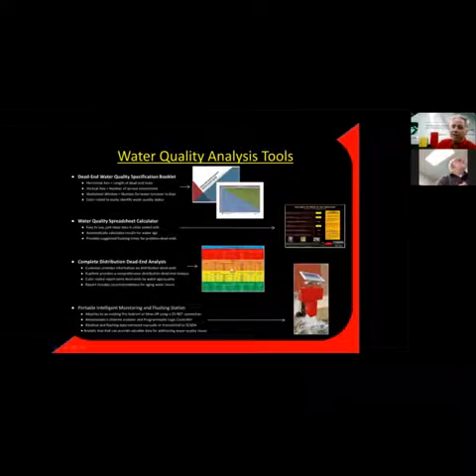Another very effective tool we have is what we call intelligent monitoring and flushing stations. This portable monitoring and flushing technology is an analytical tool that attaches to a fire hydrant. I can program it to maintain a certain residual or turbidity. It has a PLC and a chlorine sensor, and I can tell it to maintain a 1.0 ppm minimum residual and 1.5 ppm desired level, sampling twice a day at noon and at midnight.